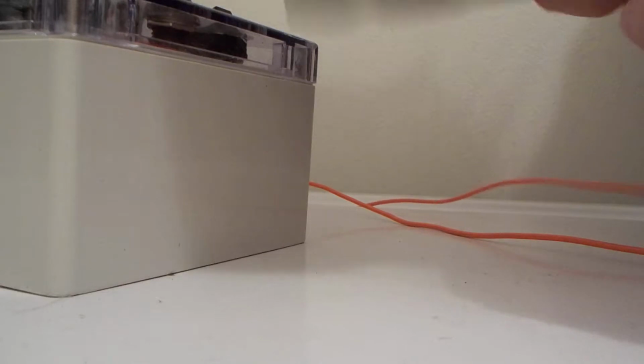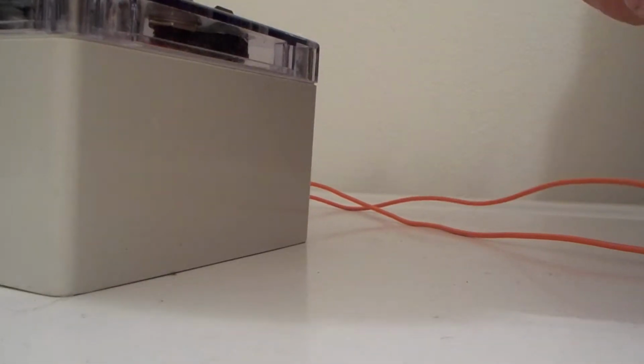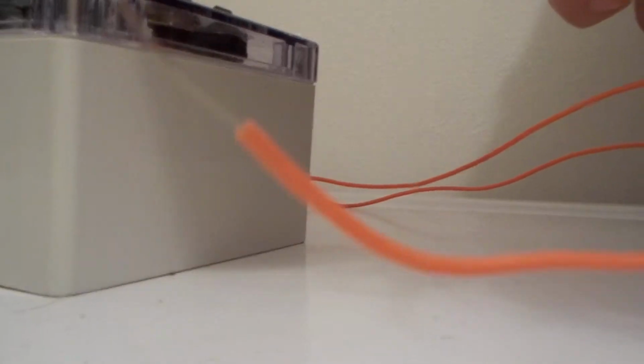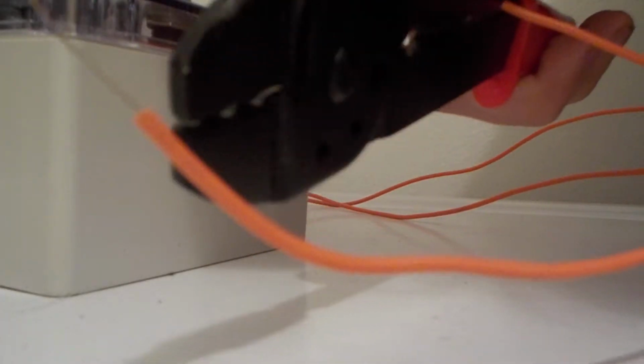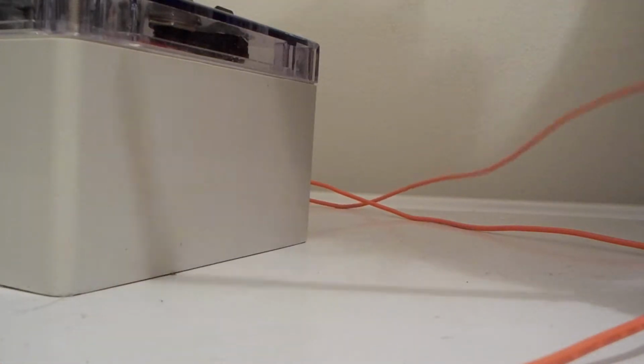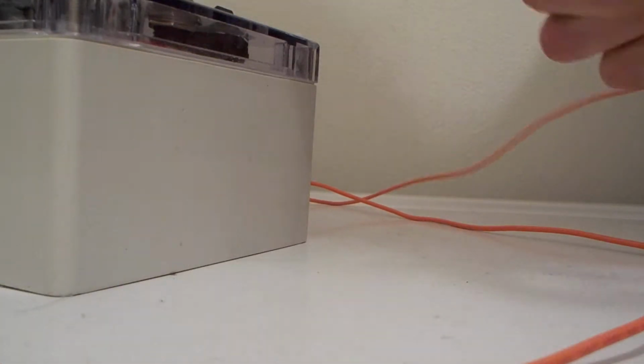They're kind of warm, as you would expect. I forget what gauge this wire is. You can see it's not too much. This is 600 volt wire. Even though it looks a lot like the 300 volt wire, you can see there's extra insulation in there. But this is 600 volt wire, and we're pushing it right up there.